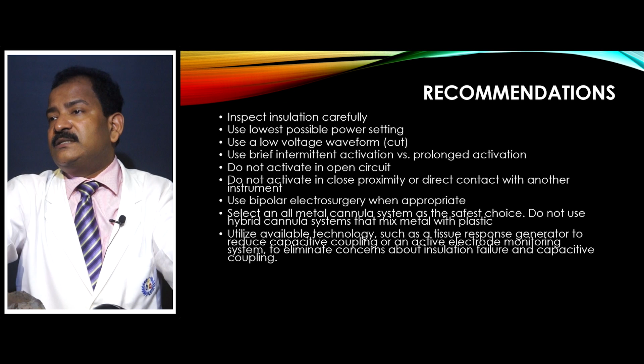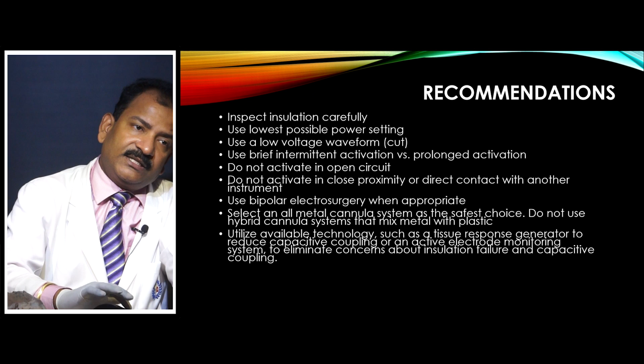And if you can utilize available technology, then use it, such as tissue response generator, which will reduce the capacitive coupling, or active electrode monitoring system to eliminate the concern about the insulation failure and capacitive coupling. So, with these few methods, if you take care, then we can minimize the complications of electrosurgery.